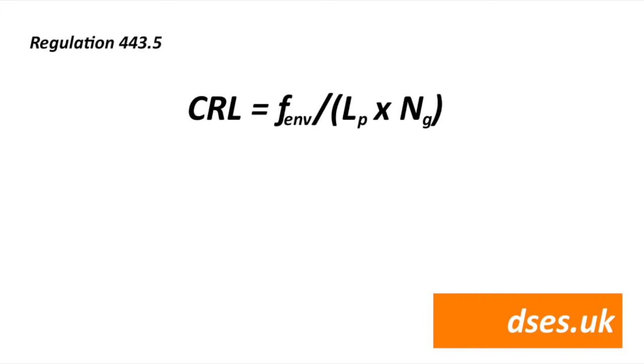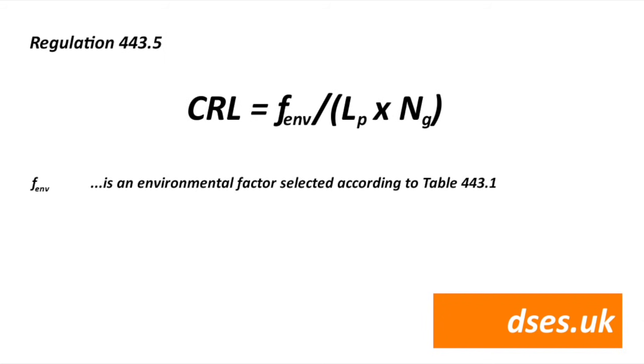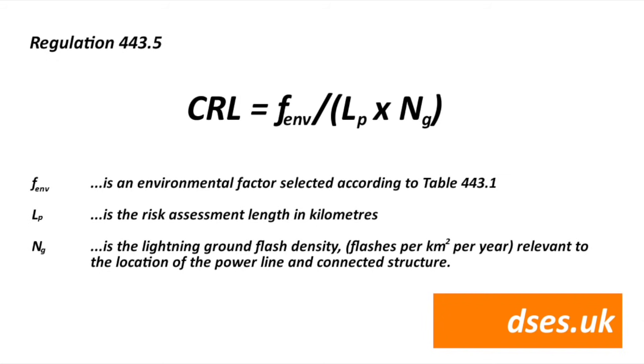So, if you want to get out of installing SPDs, you turn to Regulation 443.5, which gives you a formula for calculating the risk level. If the result is greater than or equal to 1,000, then you don't need surge protection, but if it's under 1,000, then you do. Ready for this? Let's see if we can calculate the risk for my own dwelling. Here's the formula. Calculated risk level equals FENV divided by LP times NG, where FENV is an environmental factor selected according to Table 443.1, LP is the risk assessment length in kilometres, and NG is the lightning ground flash density measured in flashes per square kilometre per year relevant to the location of the power line and connected structure.